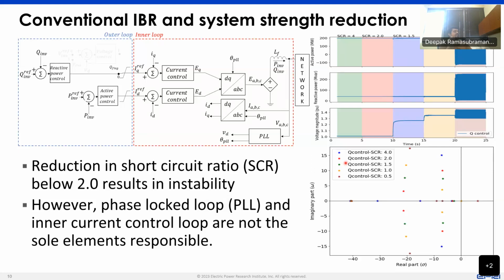So now if you just compare a conventional IBR plant, but now at the inverter level, so we're not talking about the plant level, we talk about the inverter level, it follows power control because it's trying to follow the references that are sent by the plant controller to it, and it has an entire bunch of hierarchy of control inside it. And as short circuit strength reduces, as the SCR reduces, you can start seeing an instability come up, which can be reflected both in the time domain and in the stability domain. This is not a new result. This has been reported multiple times across literature, and we know that a lot of behavior occurs in this space. But one of the things that we do have to consider here is that a lot of times this behavior that we see is not solely because of these inner loop elements. The inner loop elements do play a role, but they are not the main contributing factor for the instability that you would see as the short circuit strength reduces.